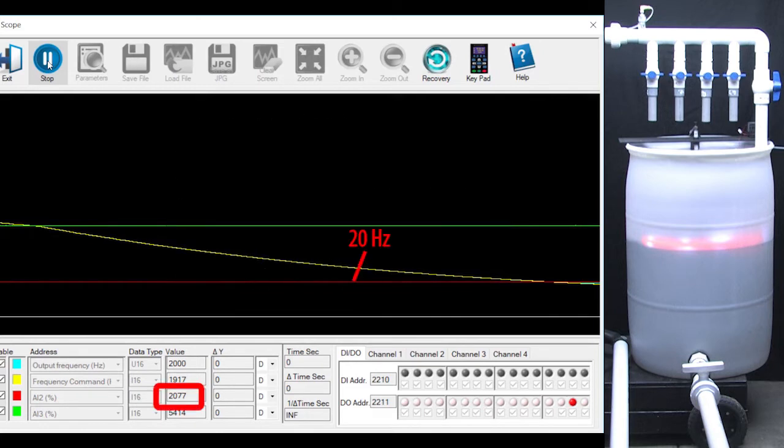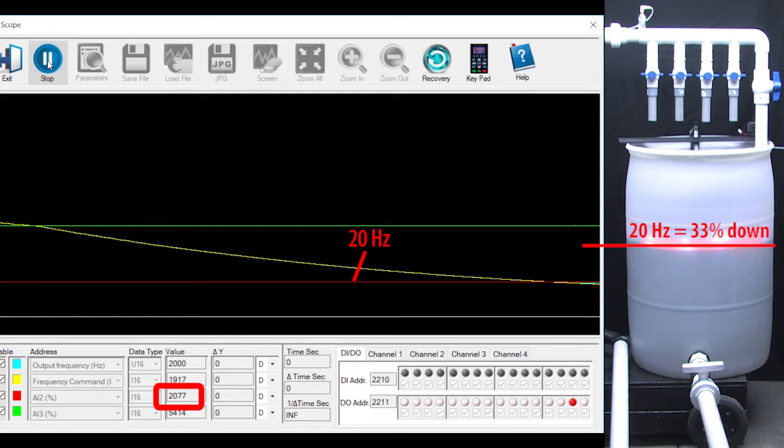That's why I set the sleep level at 20 Hz. Anything below that and this pump stops working. But since the sensor is controlling the drive speed, that means we can't fill the tank past this level.